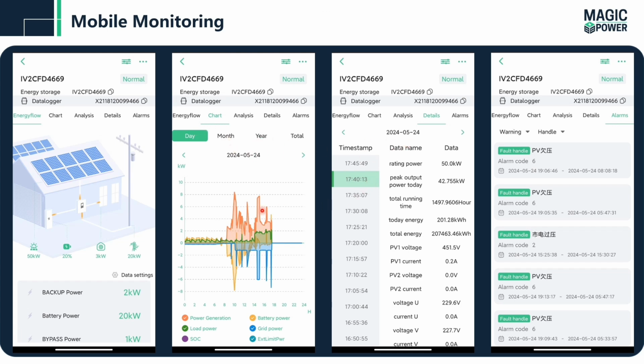The next one, if we further move into the details, we choose the date and the time slot. In that one, we can see the rated output or generation power, the battery voltages, the PV voltages, and the power grid voltages. Also, for the battery we can see the state of charge, state of health, current of the cells, and voltages of the cells. And the main thing is the temperature of our energy storage system.